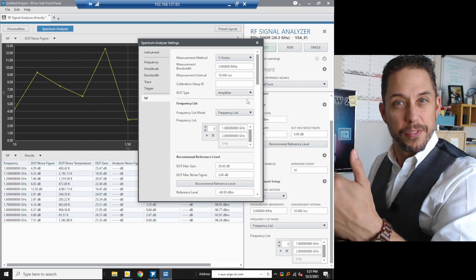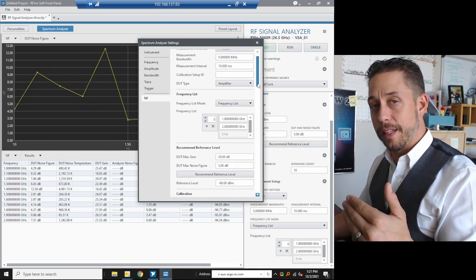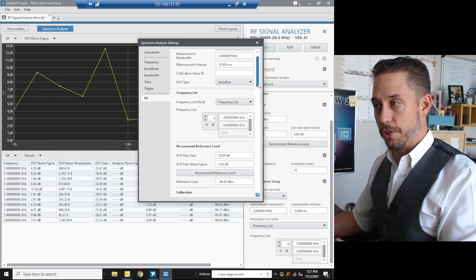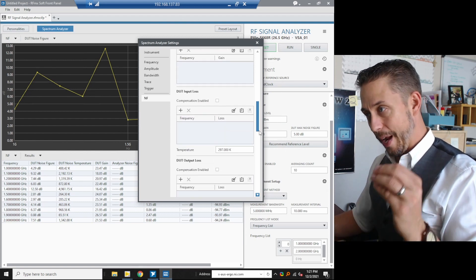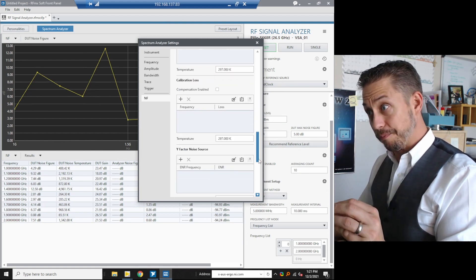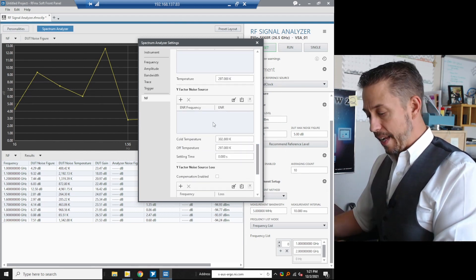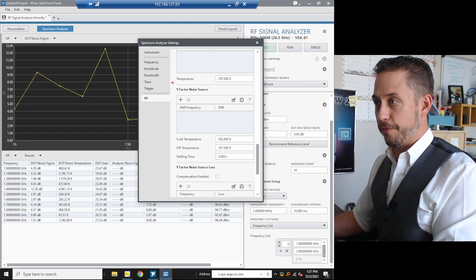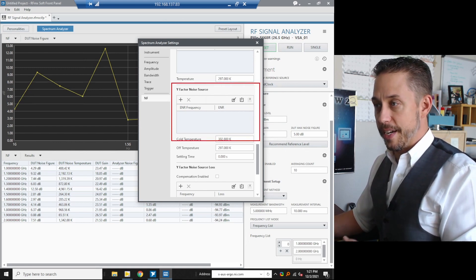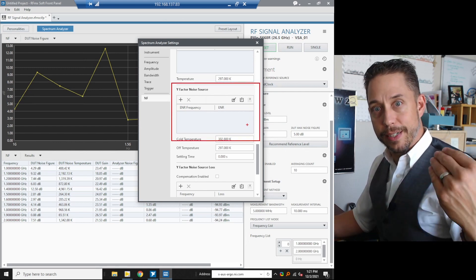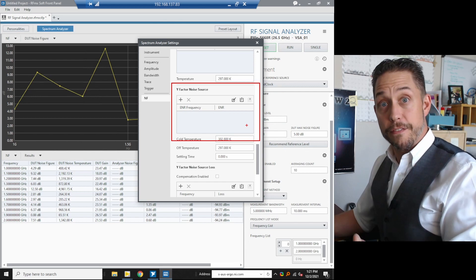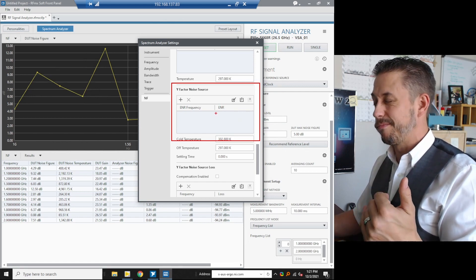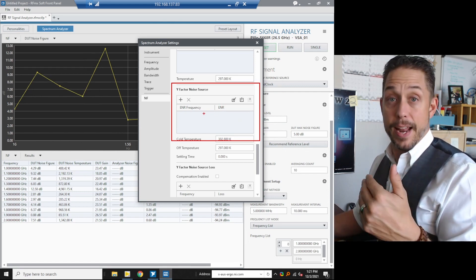By default it asks which frequencies you want to calibrate and measure at. I only want to do it at two frequencies: 1 GHz and 2 GHz. I prefer to change the mode to Frequency List — you could also use start/stop/step or start/stop with number of points, but frequency list lets me know exactly what I'm doing. I'll clear the existing list, type in 1 GHz and 2 GHz. Click the gear icon to bring up the tab to configure more of the measurement, particularly the ENR values for the noise source.